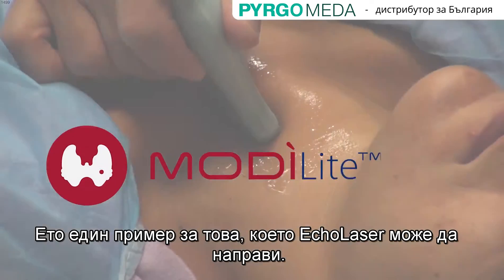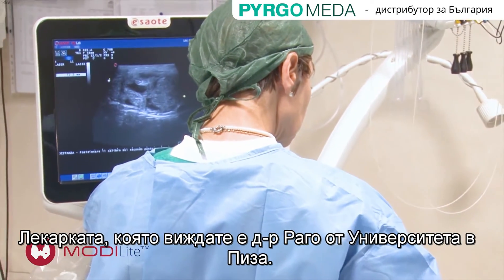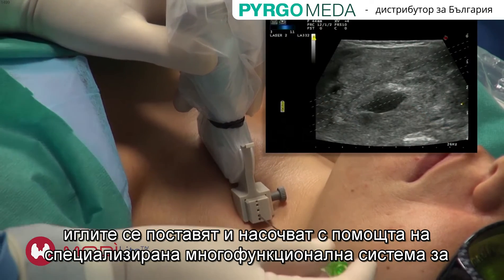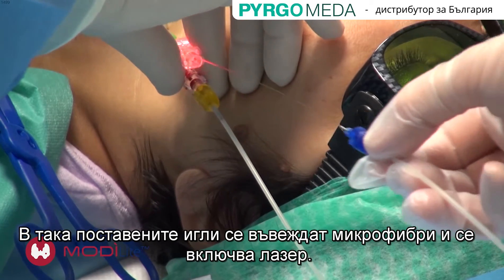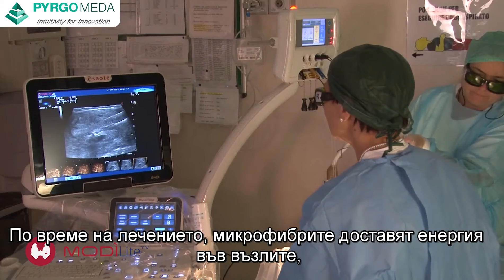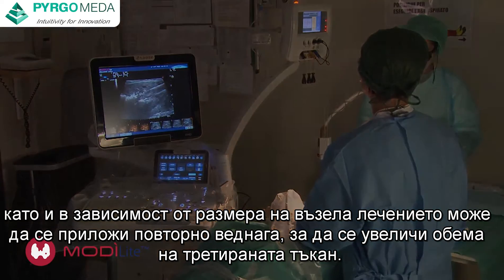Here's an example of what EchoLaser can do. ModiLite is an application for head and neck lesions. What you're seeing now is Dr. Rago at the University of Pisa. After the planning of the treatment, needles are inserted using a dedicated multi-applicator ultrasound guiding system. Inside the needles, fibers are introduced and the laser switched on. During the treatment, fibers deliver energy into the nodule and, depending on the nodule size, a second application may be necessary to increase the treated tissue volume.